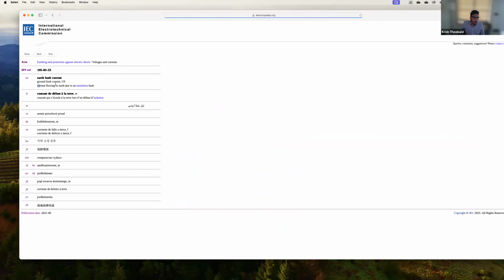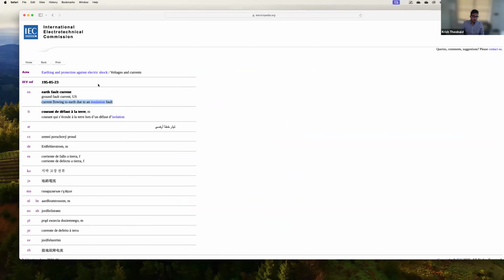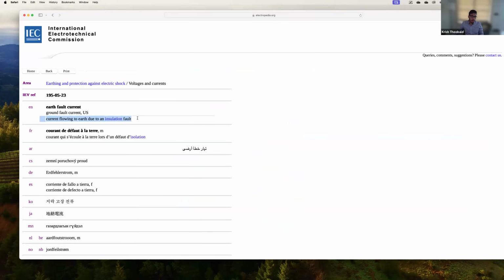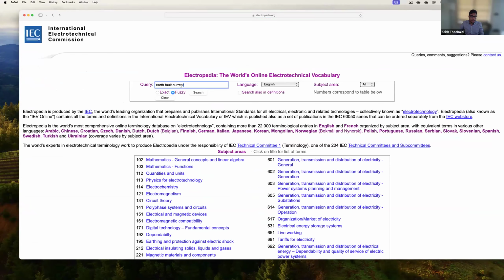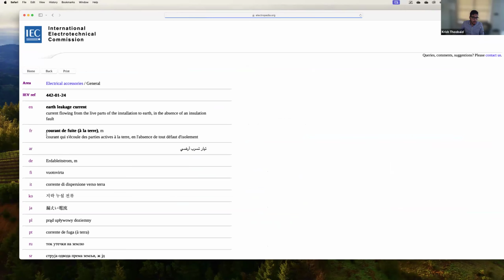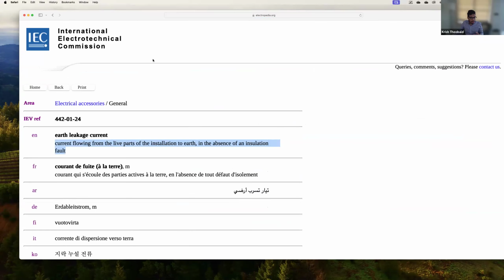See, earth fault current is current flowing to earth during an insulation fault. Whereas earth leakage current is current flowing from live parts of the installation to the earth in the absence of an insulation fault, because leakage currents are normal, whereas fault currents happen in the event of a fault. That's the difference. But to an RCD, several components of leakage may look like a fault. That is why proper sectionalizing is required.